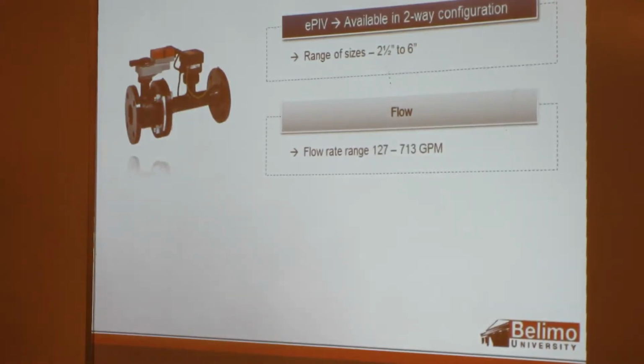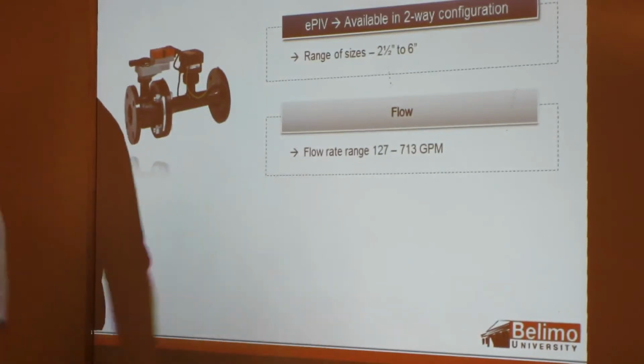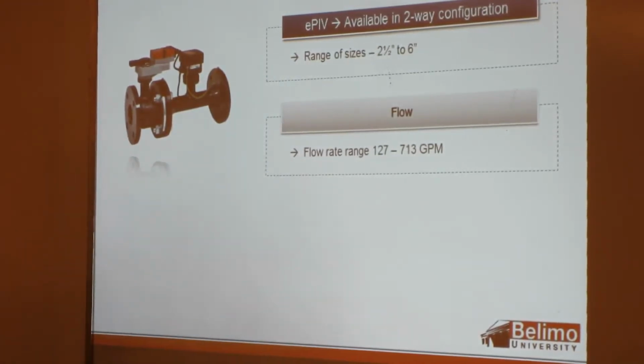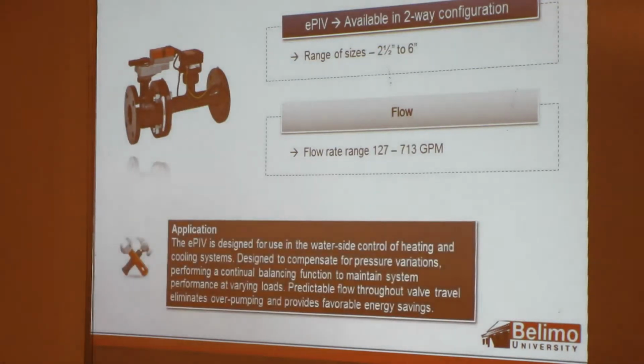Now, we will set the valves for certain GPM. The lowest will set the maximum range on that 2.5 inches, 90 GPM. Designed for use in waterside heating and cooling systems, and again designed to compensate for the pressure variations, give you the consistent flow that you're looking for.